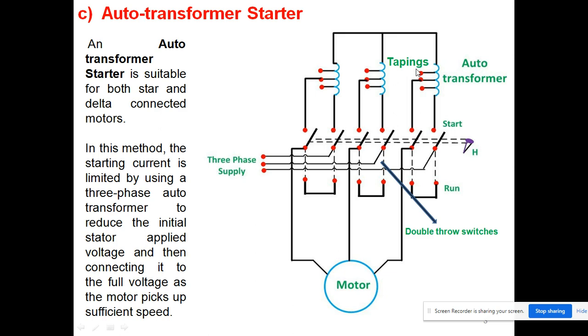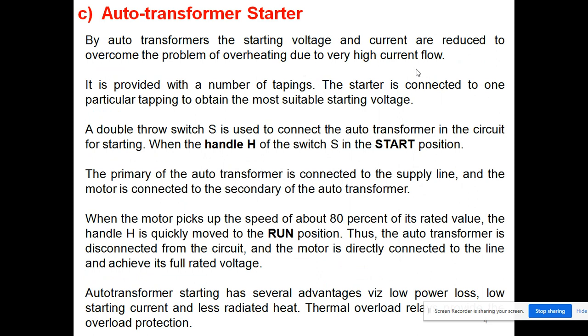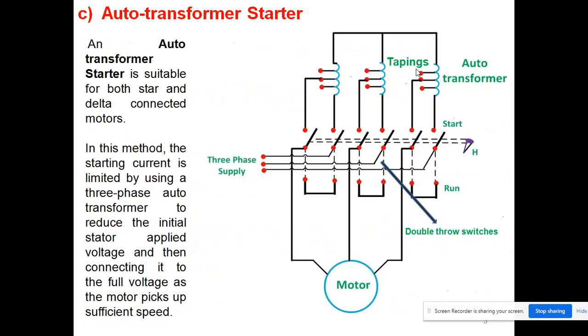When the motor runs at about 80% of its rated value, in that condition this handle moves to the run position. It means these connections will be disconnected here, and the three-phase supply is connected directly to the motor in this way.